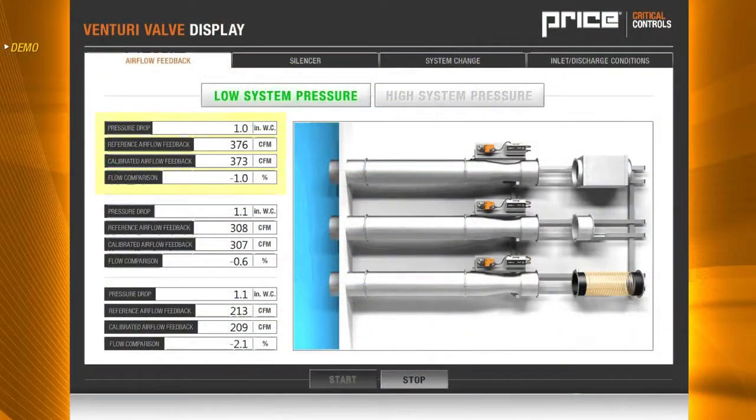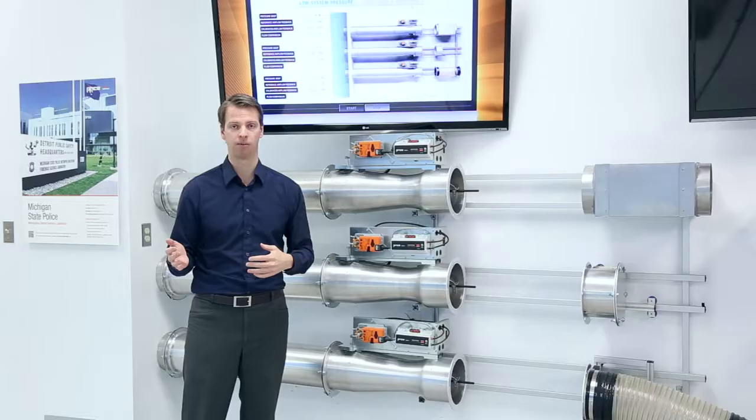You can see that on our top valve we have one inch static pressure across that valve. We have 378 on our reference air signal and 375 being provided as our calibrated signal from the Venturi valve for a difference of 0.6%. On a Venturi valve to maintain pressure independence, it needs to be within plus or minus 5% of the reference airflow.